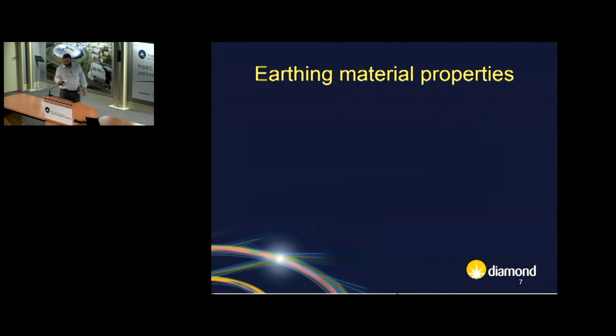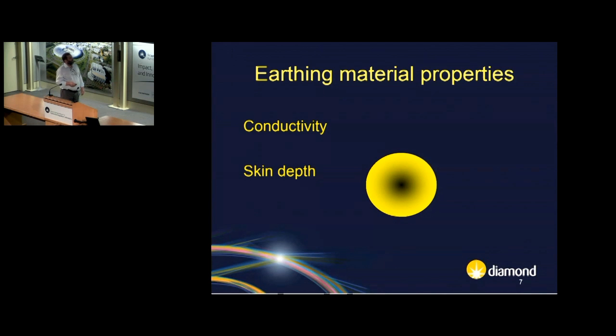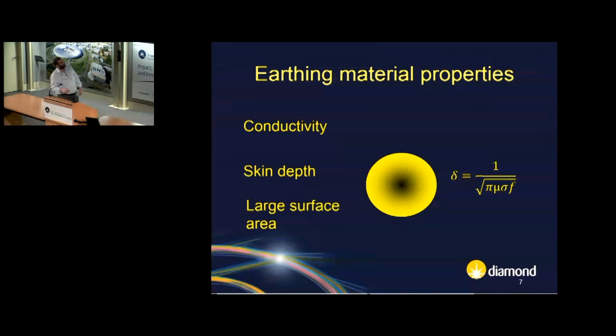So what do we use? Well, conductivity is a key parameter for an earthing system. Copper's quite good. There is a problem though, and it's skin depth. Alternating currents do not flow throughout the body of a conductor - they like to flow on the surface. The depth is given by a formula which is inversely proportional to the frequency, the conductivity, and the magnetic permeability.